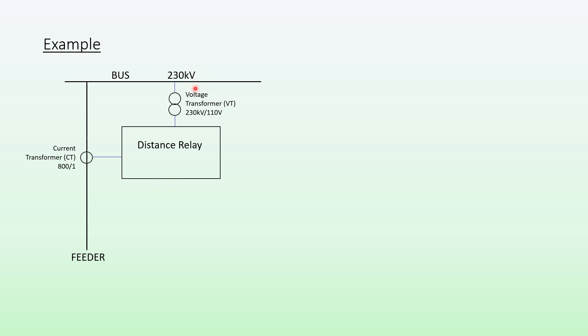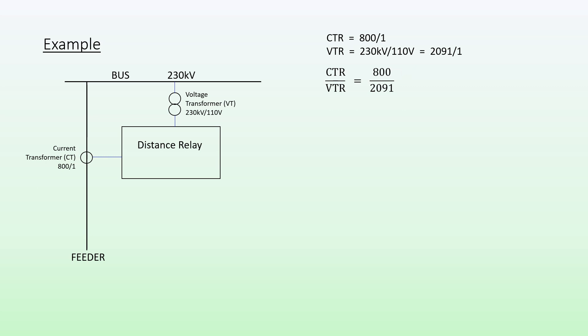Let's do an example. Here we have a distance relay connected to a 230 kV bus by means of a VT rated 230 kV to 110 volts, and the relay is also connected to the feeder by means of an 800 to 1 amp CT. This gives us a VT ratio of 2,091 to 1, so our CT ratio over VT ratio is 800 divided by 2,091, which equals 0.383.